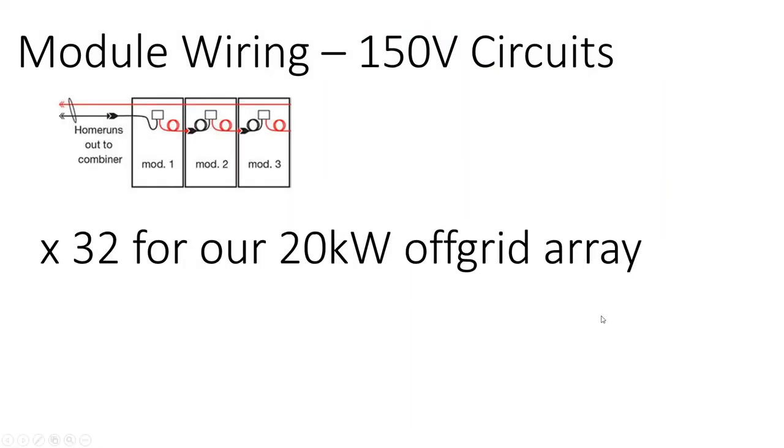Well, a lot of off-grid products are, it's weird, but the charge controllers are not for 600 volts. They kind of come out of an industry where, you know, solar modules were more expensive. And instead of using power optimizers for shade mitigation, they just did less solar modules and more circuits so that the shade only impacted one circuit, not the others. And so if you only had 3 modules on a circuit, only 3 modules get impacted and not 8.